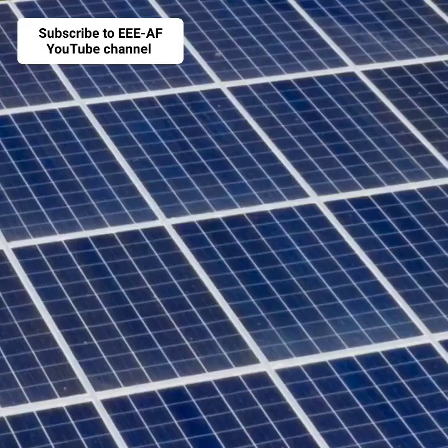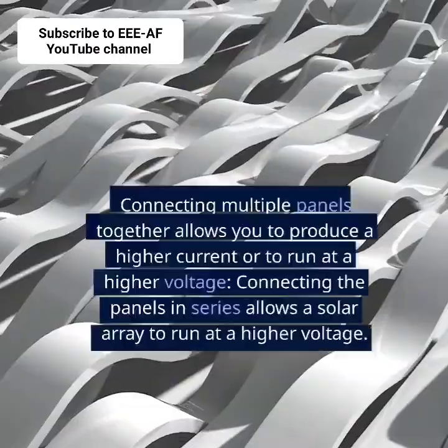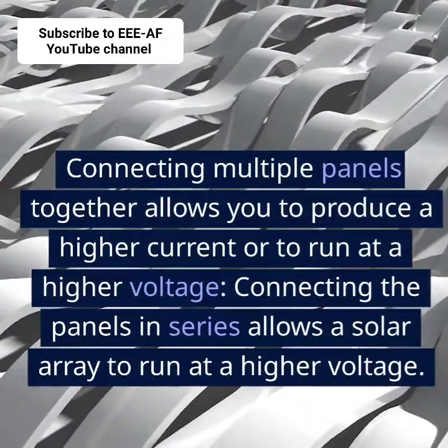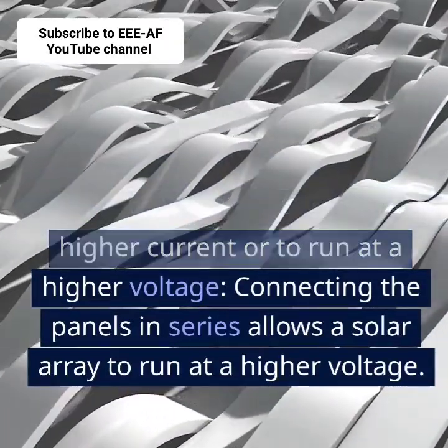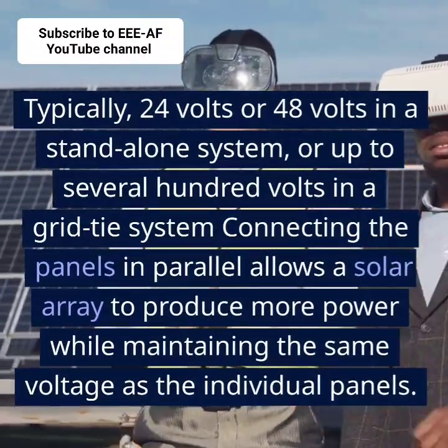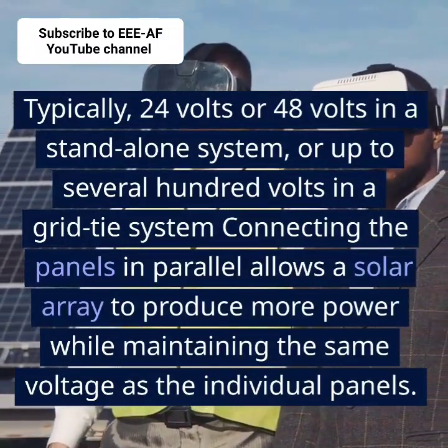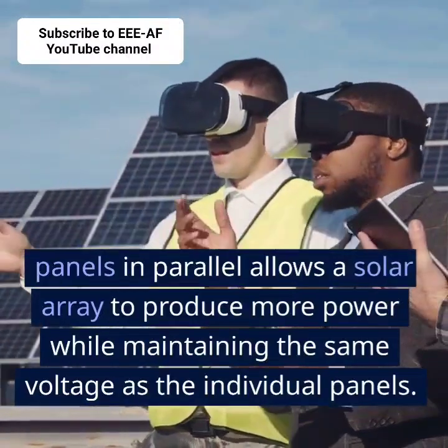18 volts. Solar panels can be linked together to create a solar array. Connecting multiple panels together allows you to produce a higher current or to run at a higher voltage. Connecting the panels in series allows a solar array to run at a higher voltage. Typically, 24 volts or 48 volts in a standalone system, or up to several hundred volts in a grid tie system.